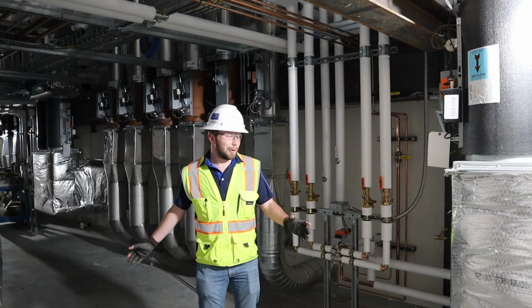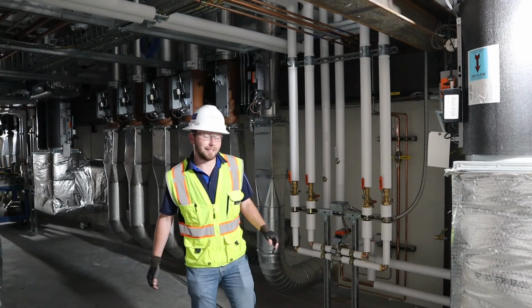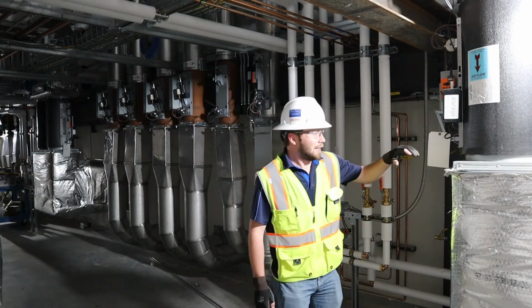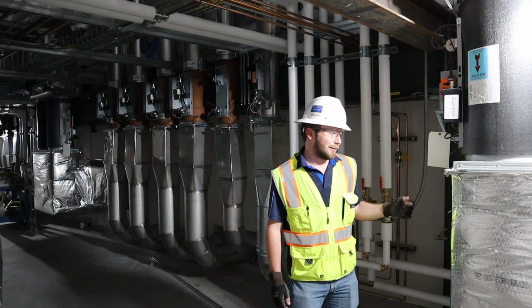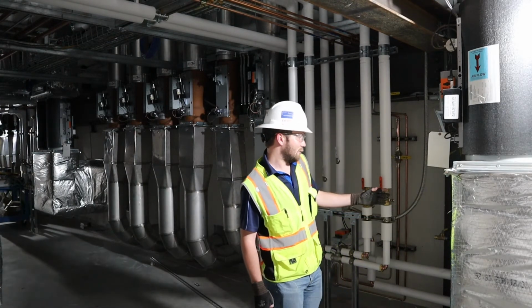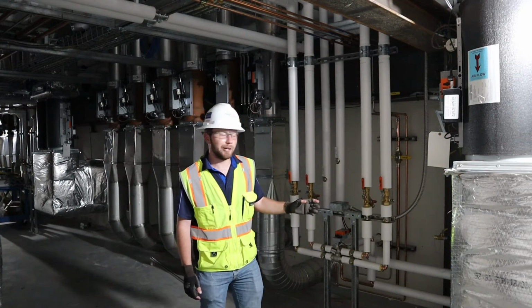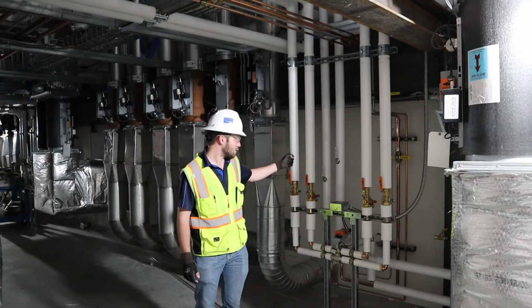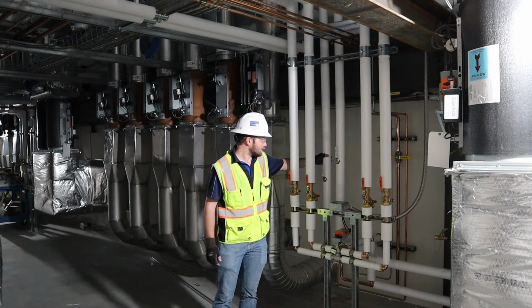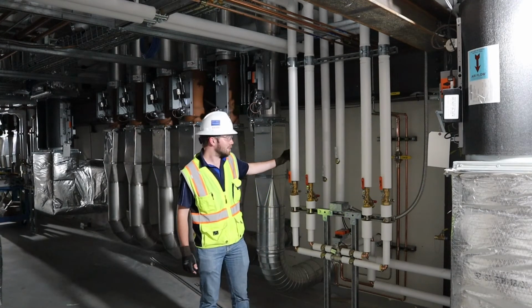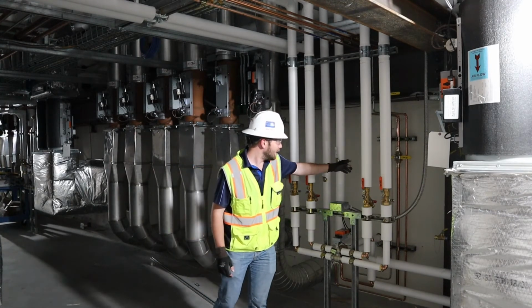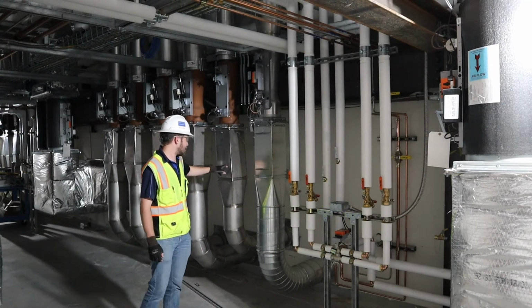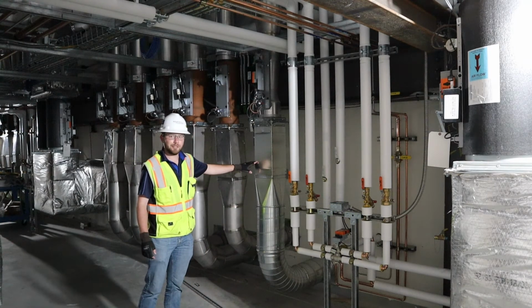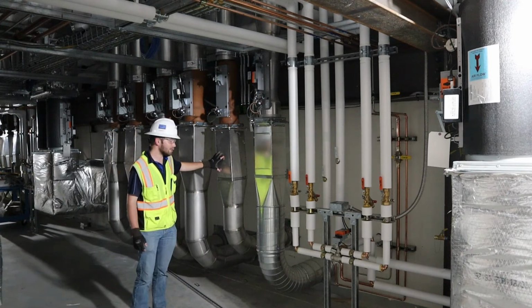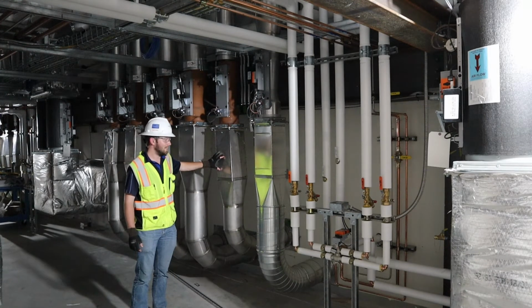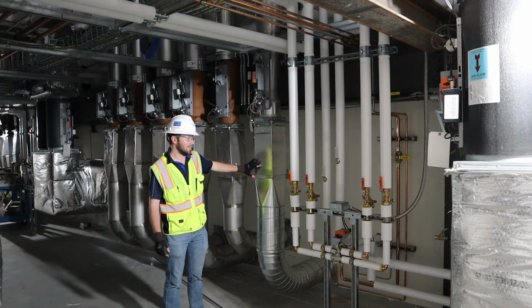This is a typical intersection of the interstitial space. Every lab has supply air going to it. On each supply into the labs, there is a heating and cooling coil. There's the water for each of those coils. Process chilled water for each of the labs. And then we have the house gases and task exhaust and general exhaust for each of the lab. The task exhaust is all stainless steel welded duct, and the general exhaust is galvanized.